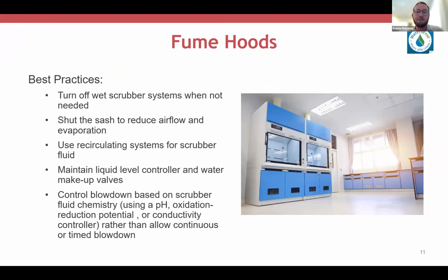With that said, here are some of the best practices to consider. First, if it's safe to do so, turn off your wet scrubber system when it's not being used or when the fume hood's not being used. As I just mentioned, be sure to shut your sash and minimize the air volume being ventilated from the fume hood. This reduces the evaporation from wet scrubbers and the cooling tower, and can improve energy efficiency.